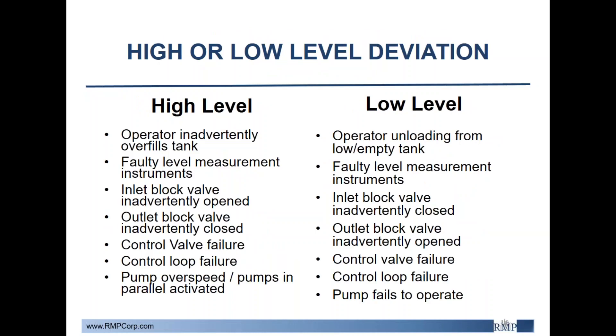Moving on to high or low level deviations. Causes for high levels could include an operator inadvertently overfilling a tank, or in contrast, unloading from a low or empty tank. There could also be faulty level measurements indicating either high or low levels. The inlet or outlet block valve of a tank being open or closed could also lead to high or low scenarios. Additionally, as with other deviations, control valve or control loop failures or pump over-speeding or failing to operate can also contribute.